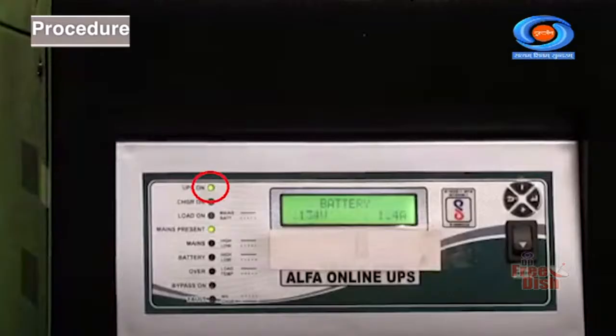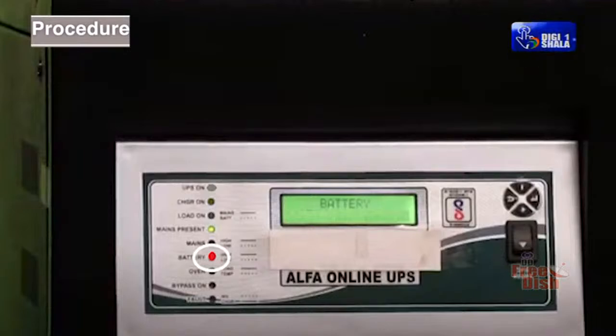If the UPS operates on load in battery mode, then the battery LED lights up. It indicates the UPS is in online operation. If the UPS does not operate on load in battery mode and immediately returns to online operation and lights up the red LED, it indicates the backup time is too short and the battery is to be replaced or recharged.